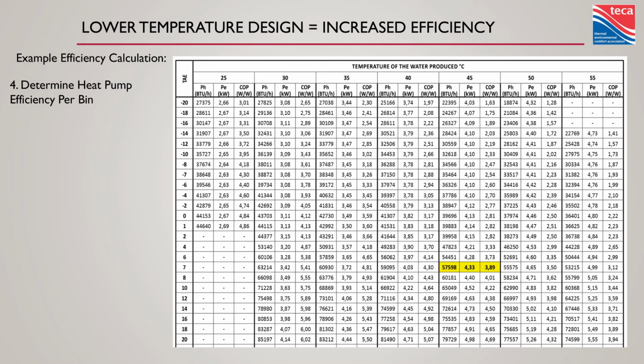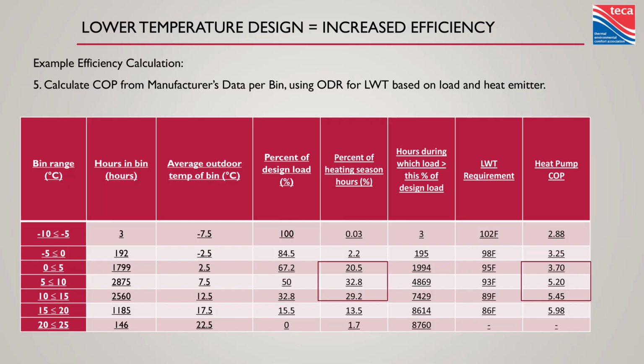Look at this. 32% of the year, I've got 520% efficiency because I only need 93 degree water to heat that space because it's 50% of the design load. 29% of the year, 545% efficient. Huge, huge numbers, much better than what's on the rating plate, certainly better than the number on the design condition, but these are the largest parts of the year. So you could then take that by the number of hours, start running some numbers on what you pay for hydro, and you can start figuring out what this is going to cost to operate.